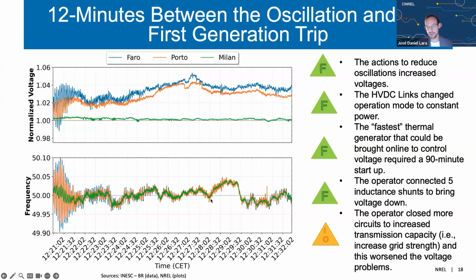And then at some point, we have this dropping of the frequency, which is the market action, but the voltage is already pretty high in the regions of Faro and Porto, right? So the operators realized that they need to start bringing the voltage under control. And in the report, it actually says that the fastest thermal generator they could bring online to provide voltage control was a 90-minute startup. So they could actually get it online before 2 in the afternoon.